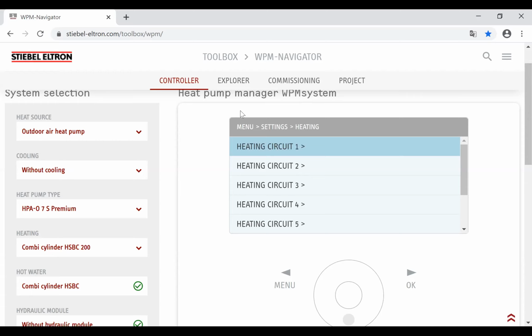As far as, A, comfort in the house, and B, the actual power usage. So we can achieve better comfort with lower power usage by running mixers and running the water through all the time and just adjusting the temperature of that water. You get fewer problems with overheat and fewer problems with the temperature outside plummeting. There could be a 2-hour lag until the temperature inside goes down, and then the pump has to turn on to reheat the slab to try and catch up for that temperature drop happening inside. It's quite interesting when you actually start looking at the data.